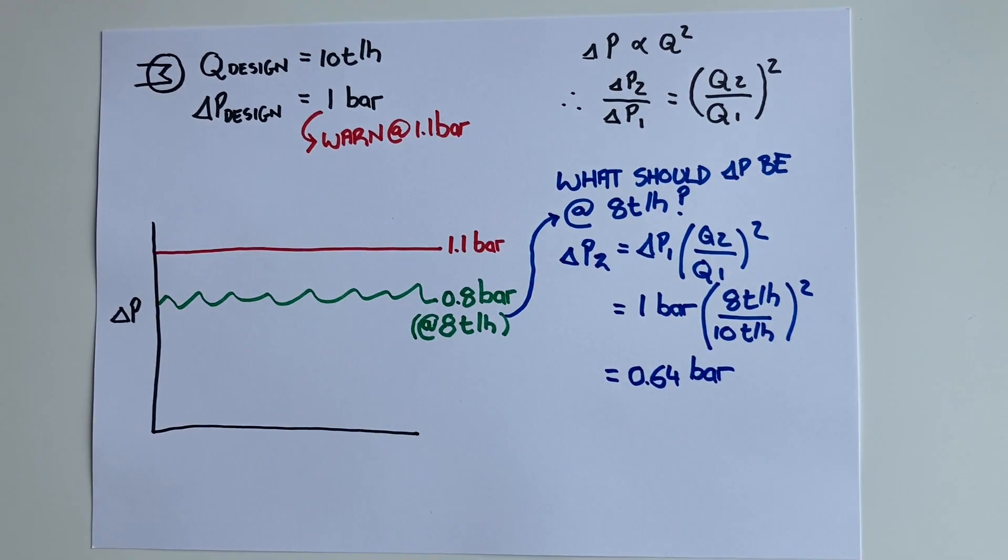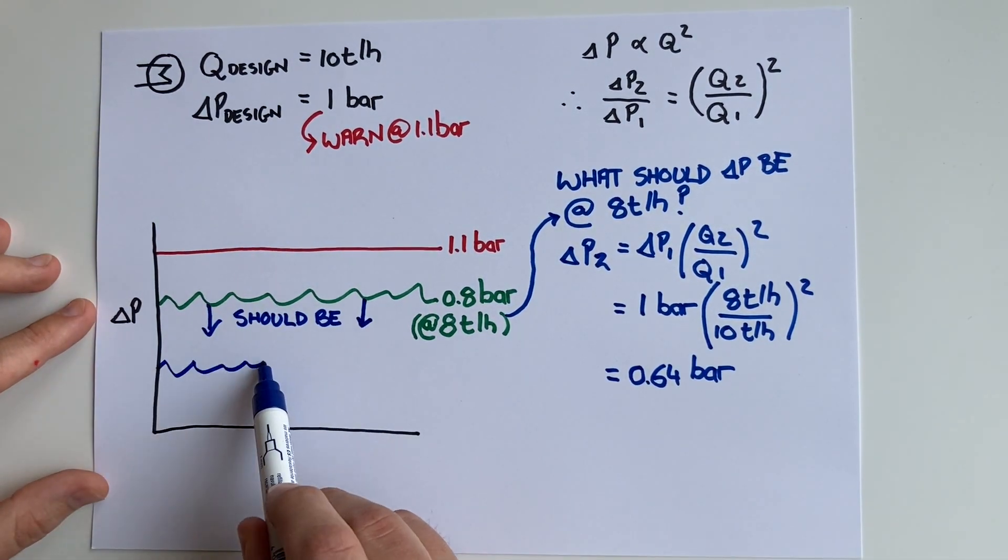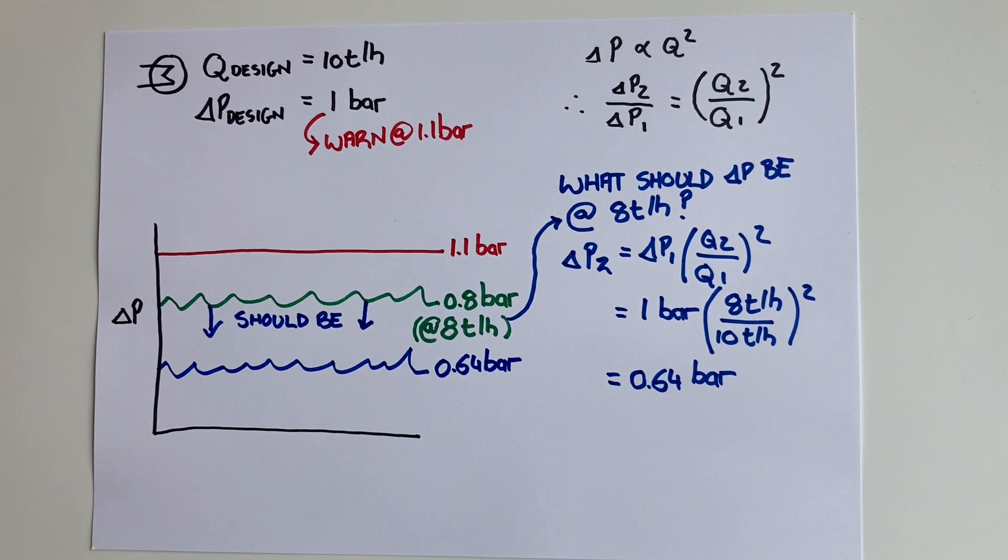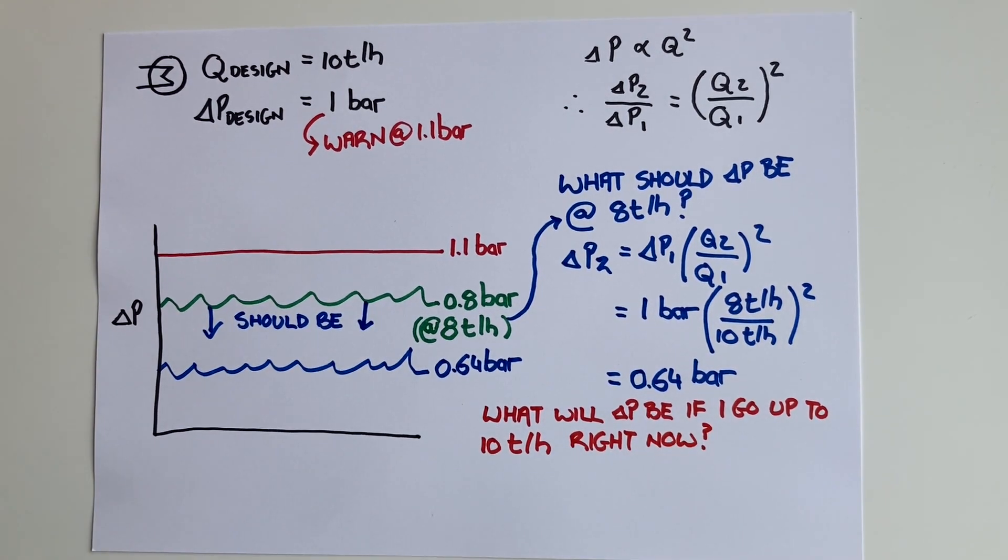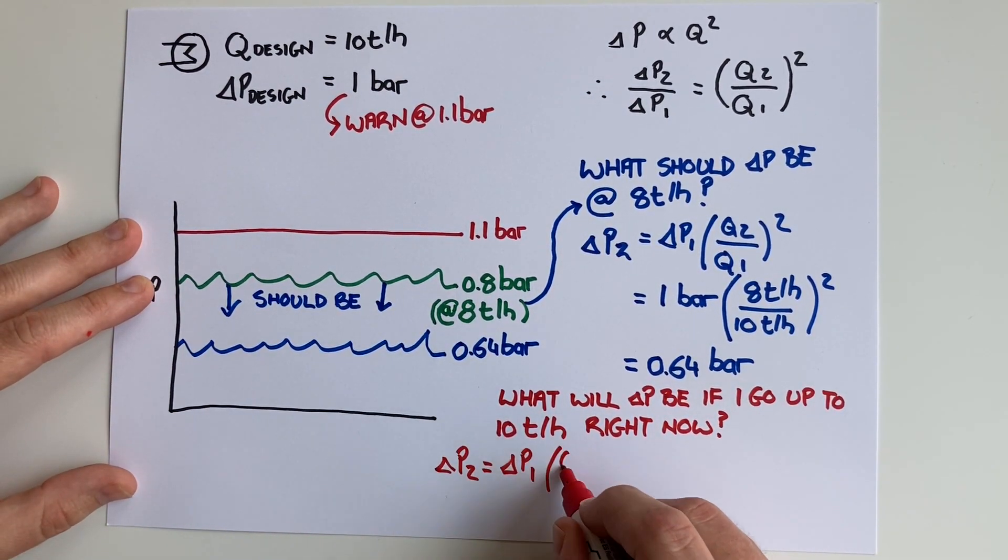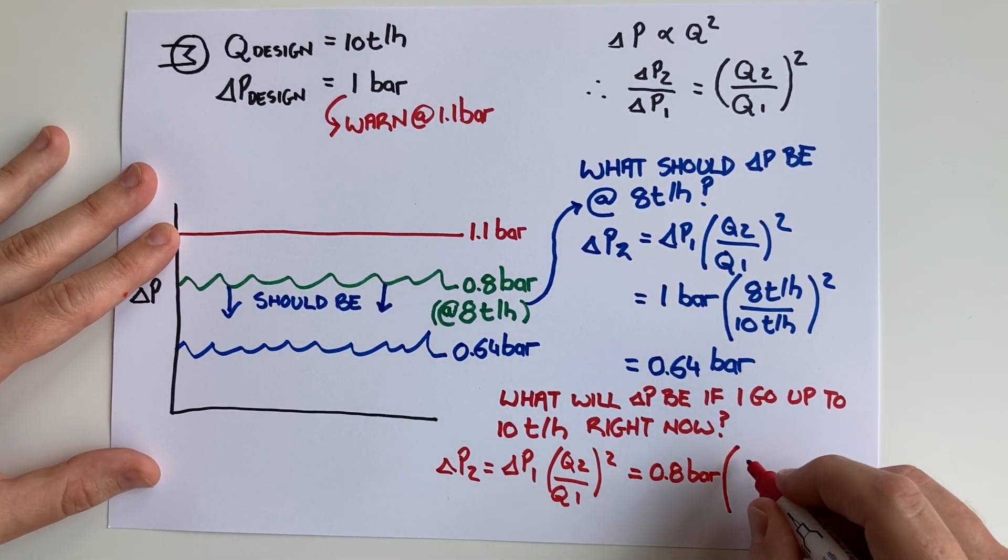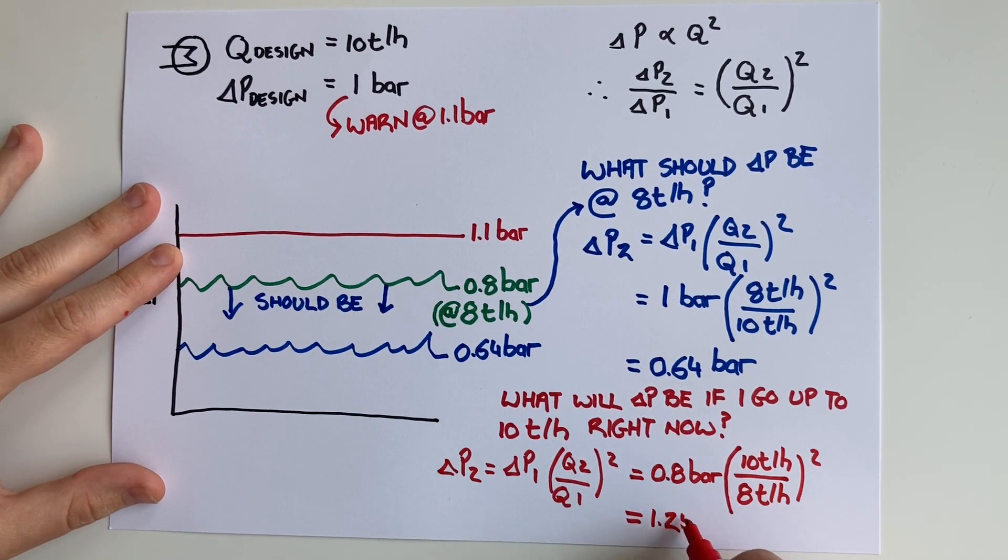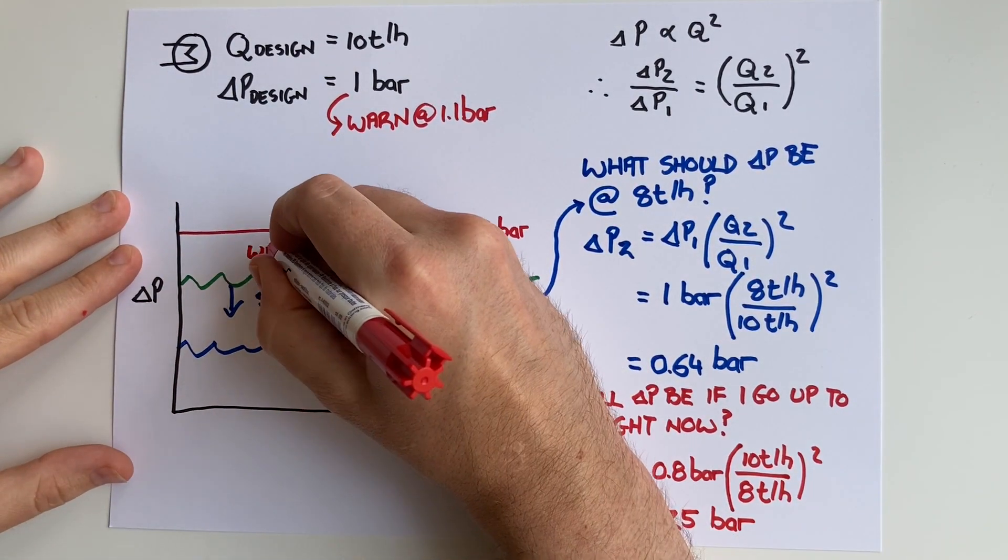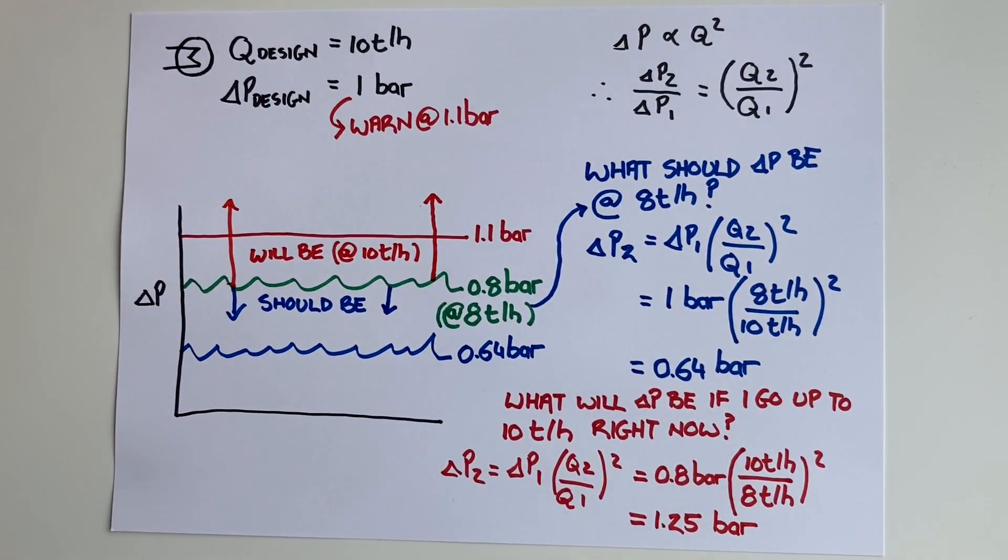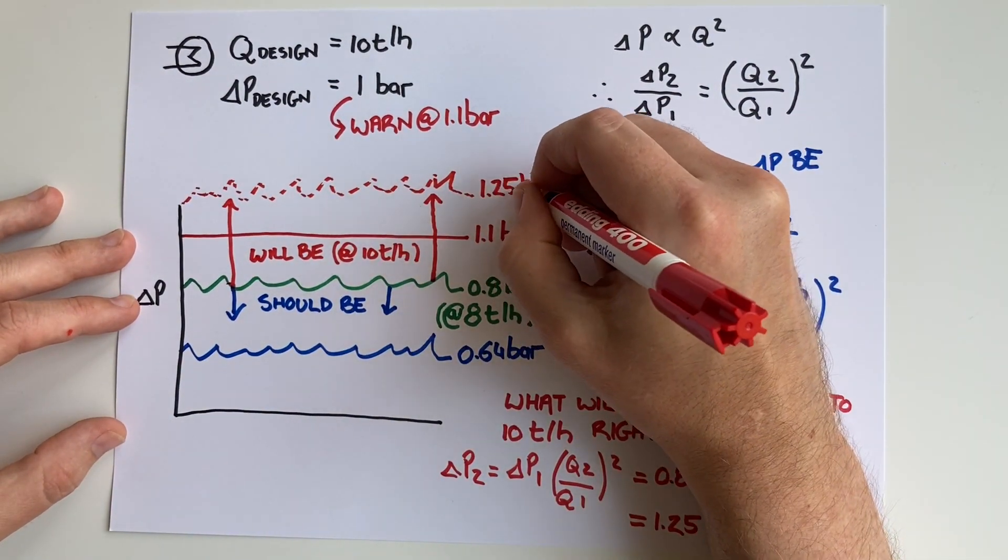What we should do is something we call normalizing the pressure drop. We take the situation as we have it right now and say that since we're not running at design flow rate, we should calculate what the pressure drop would be if we increase the flow rate to the design rate right now. We do this using the exact same equation. So our 0.8 bar at 8 tons per hour actually equates to a pressure drop of 1.25 bar at the design flow rate - 25% more than it should be. If this was the situation in my plant, I risk that I would not be able to process at my design capacity if I haven't oversized my pump or compressor enough.